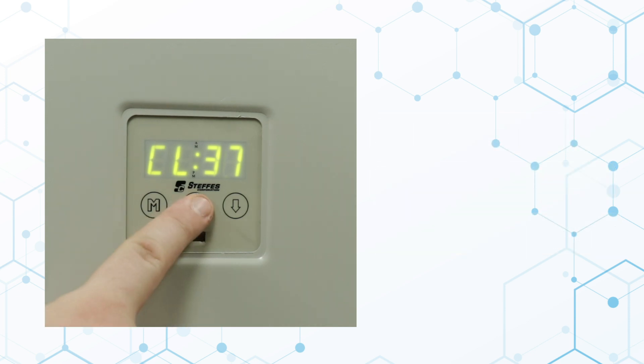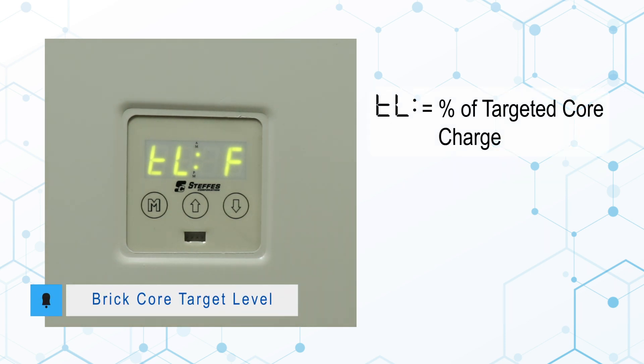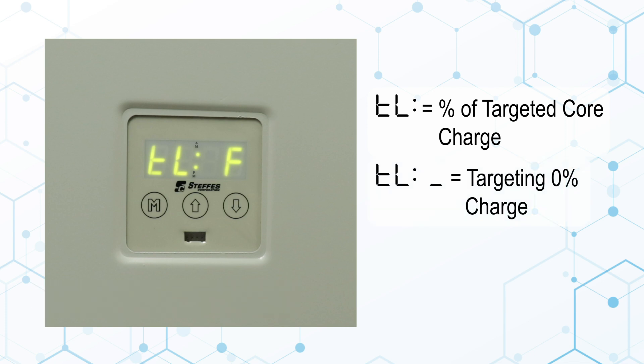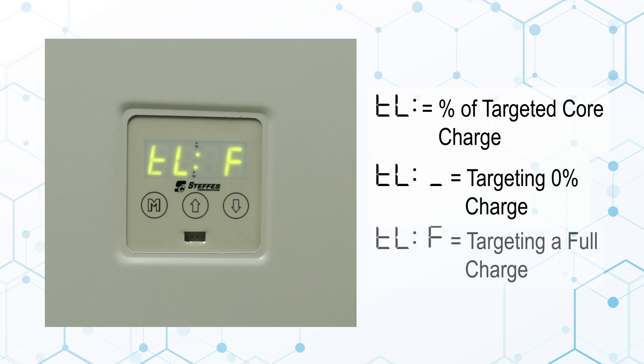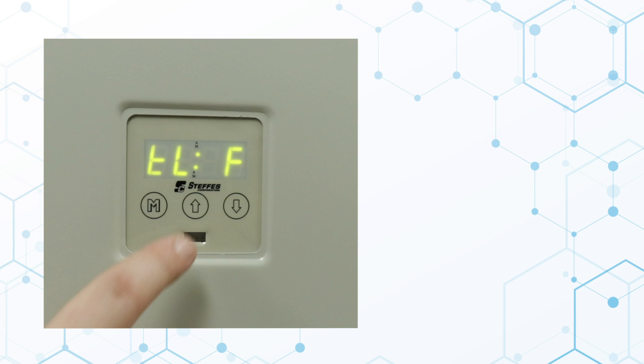Press the up arrow once more, and the display will show TL and a number, indicating the current percentage of brick core charge targeted by the hydronic system. TL underscore indicates the system is not targeting any heat in the brick core, and TLF indicates a full core charge target level. Press the up arrow again to return to the normal operating display.